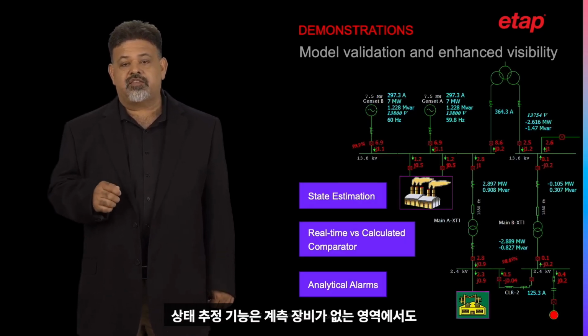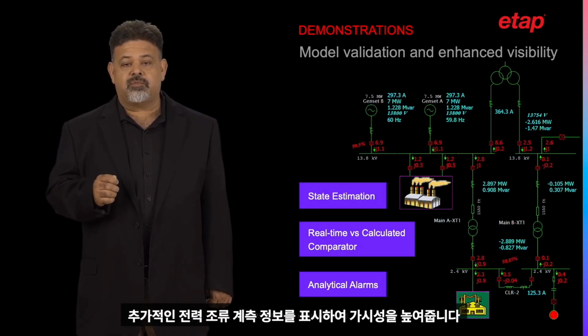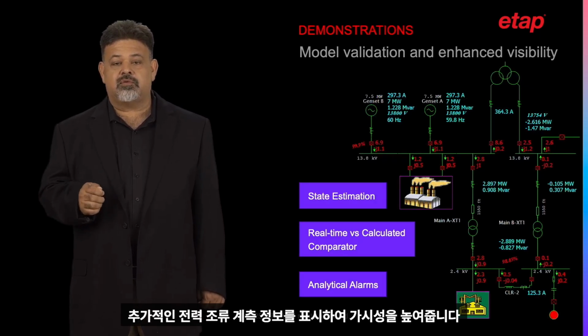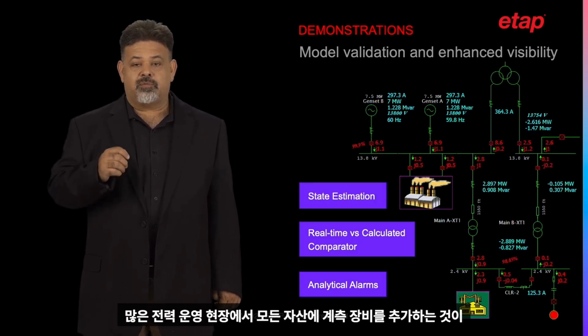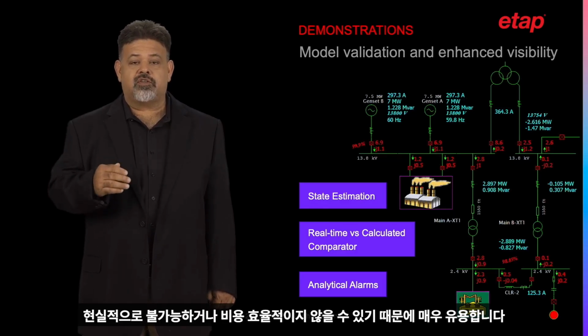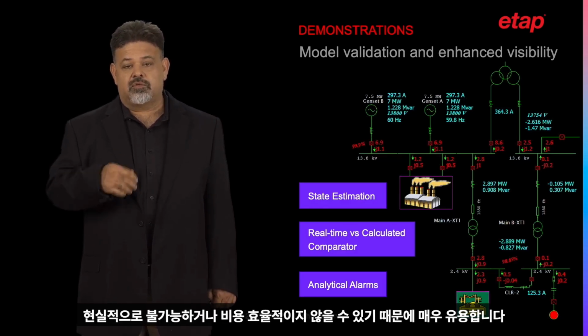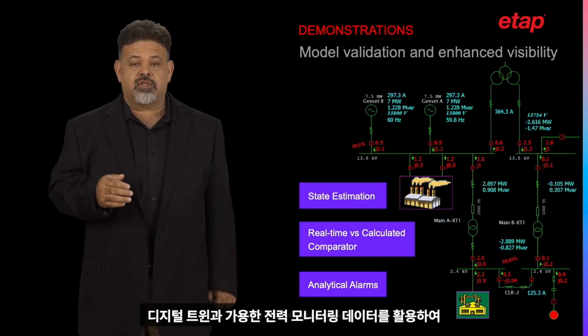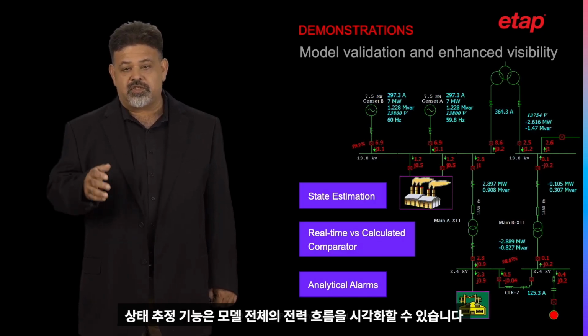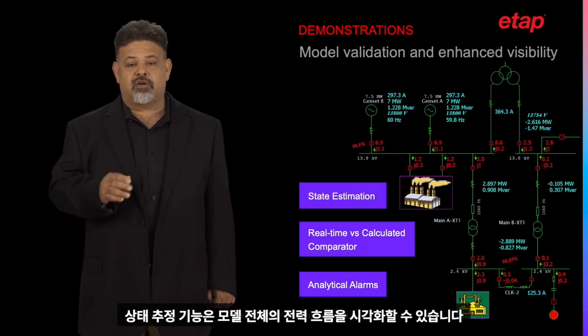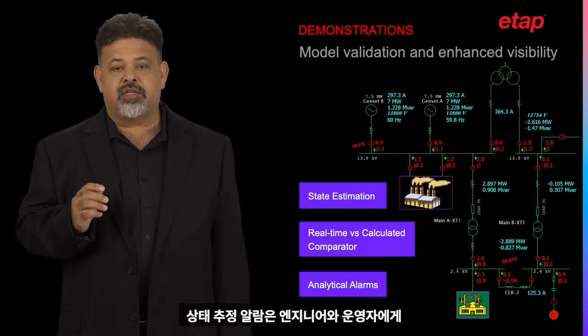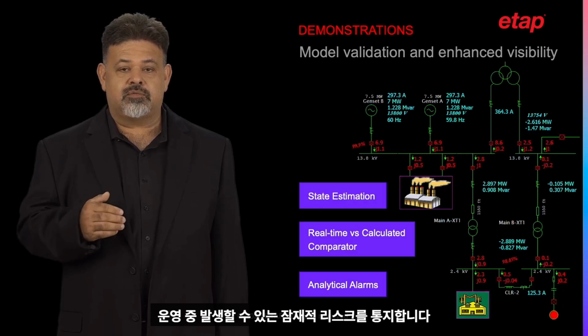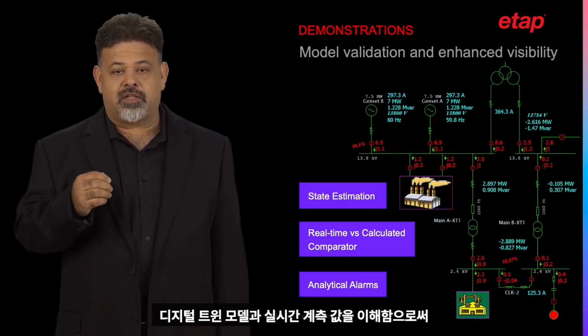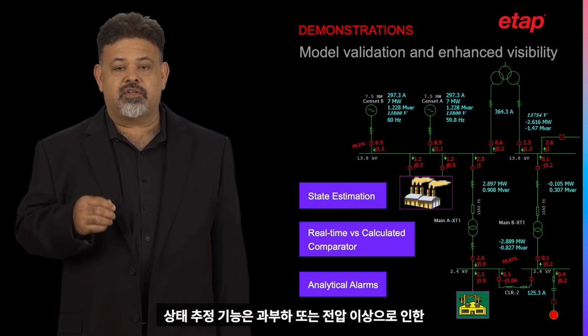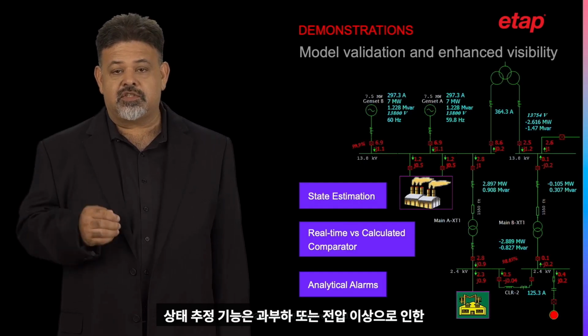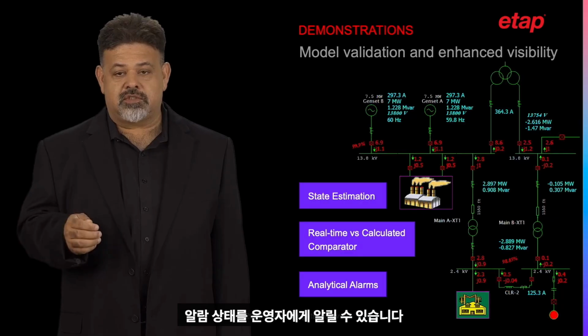The state estimation enhances visibility features, displays additional power flow measurements in areas where no instrumentation is available. This is particularly useful as for many electrical operations, it may not be feasible or cost-effective to add power monitoring instrumentation to all their assets. Leveraging the digital twin and available power monitoring data, the state estimation feature can make visible the power flow across the model. State estimation alarms notify engineers and operators of potential risks with the operation. By understanding the digital twin model and the live measurements, the state estimation feature is capable of notifying operators of alarm conditions due to overload or operating bus voltage.